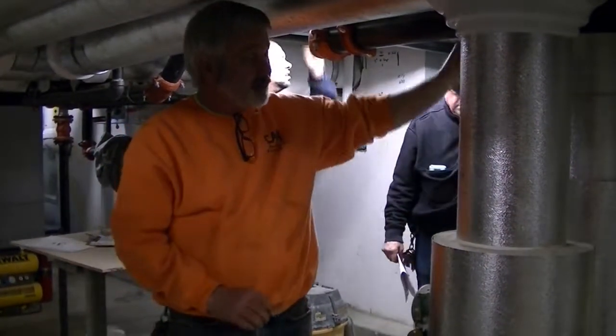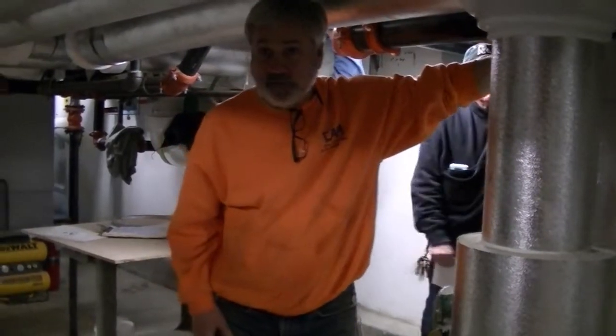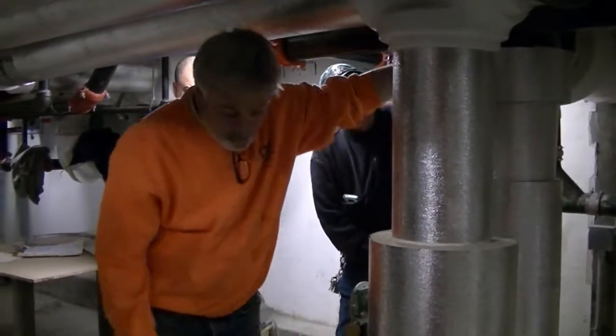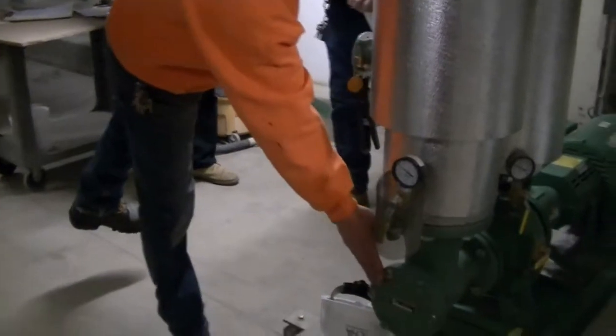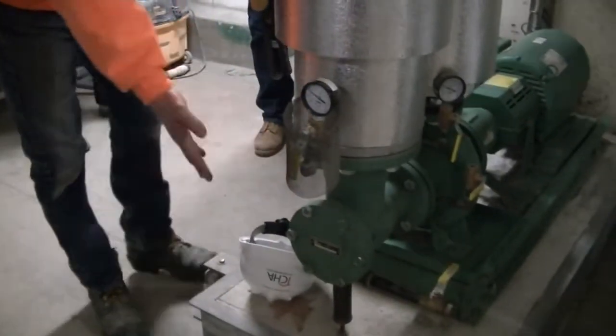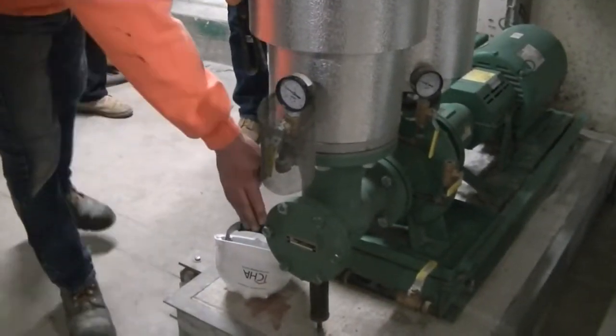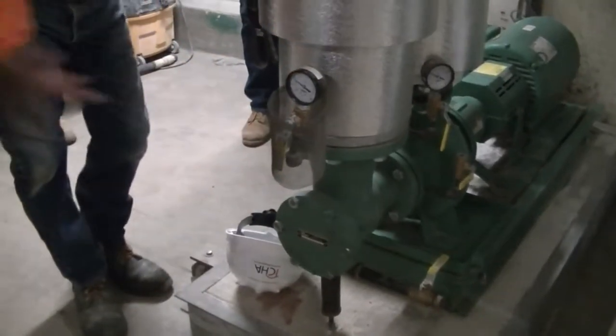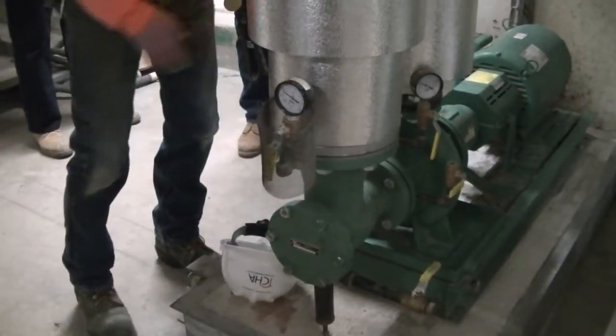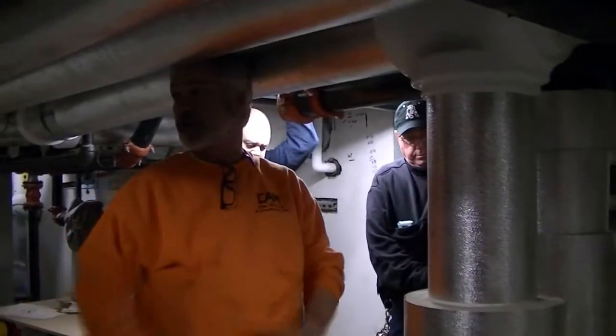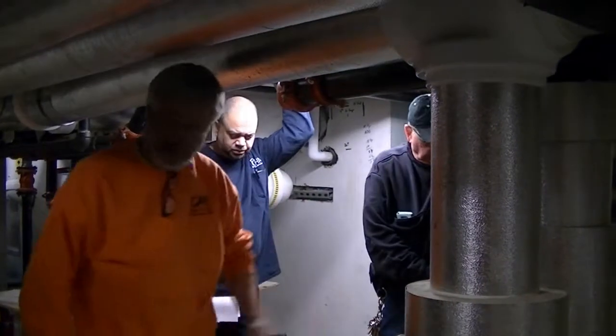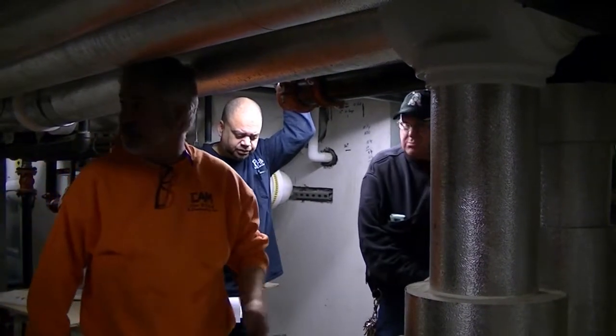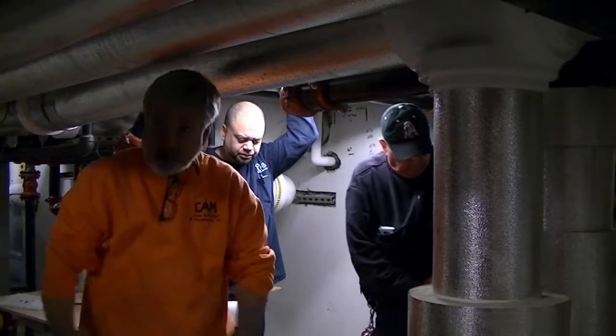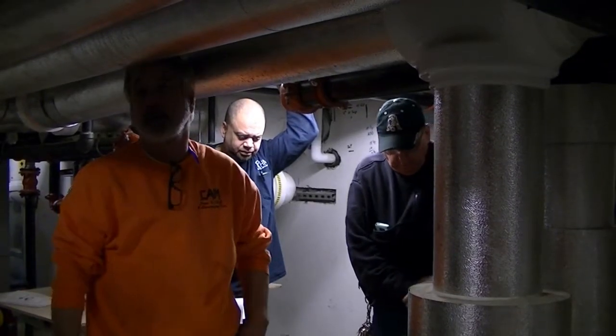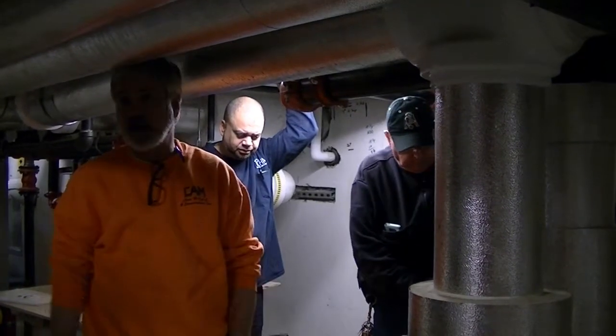Your isolation valves here. There's a check valve and a balancing valve located above it. There's a suction diffuser down in here. Periodically, every couple of years, you're going to pull this out, clean it, put it back in. Of course, you're going to isolate it first, kill the pump, isolate the valve, pull out the diffuser, clean it up, put it back in, inspect it for any debris that might have migrated in. If something, you know, is not supposed to be there, you make a phone call. Okay? Very odd that you would find anything in there.